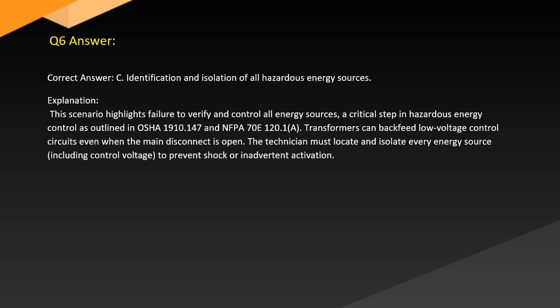Transformers can backfeed low-voltage control circuits even when the main disconnect is open. The technician must locate and isolate every energy source, including control voltage, to prevent shock or inadvertent activation.